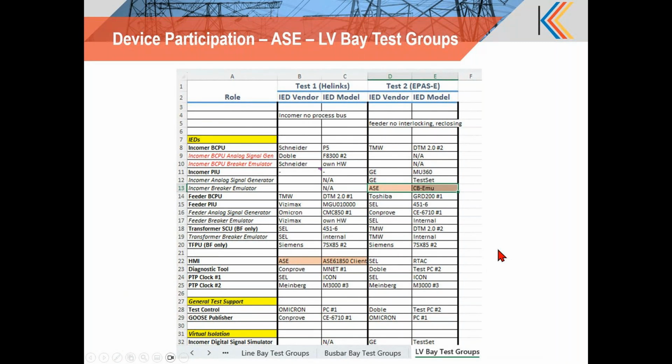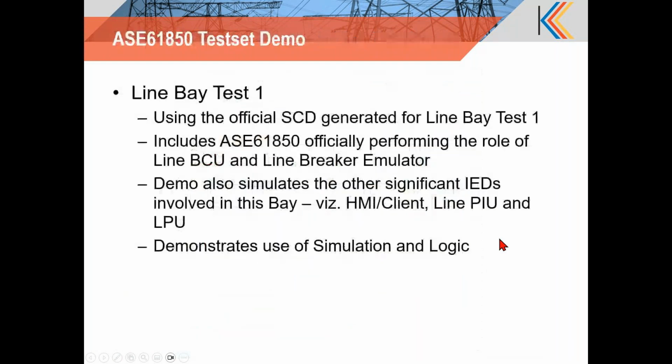The ASE test set being a flexible IED, it can act either as a client, a bay controller unit, a server, or a monitoring device. So we could do all these tests without any issues.